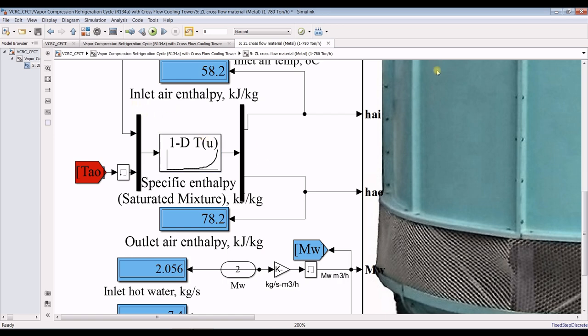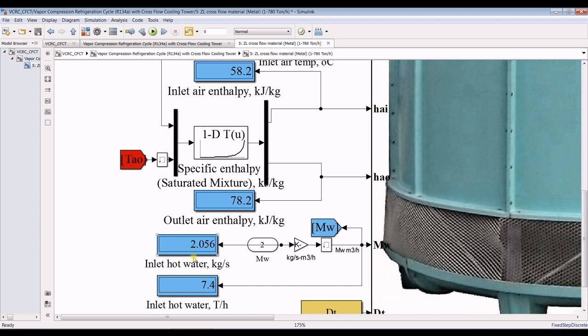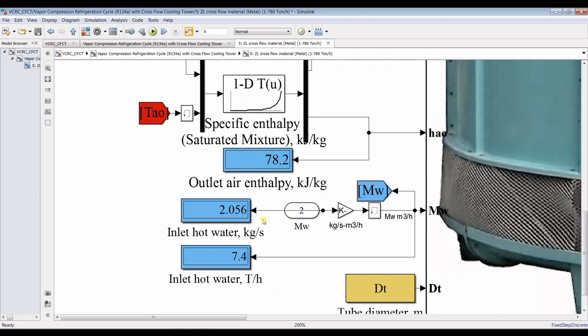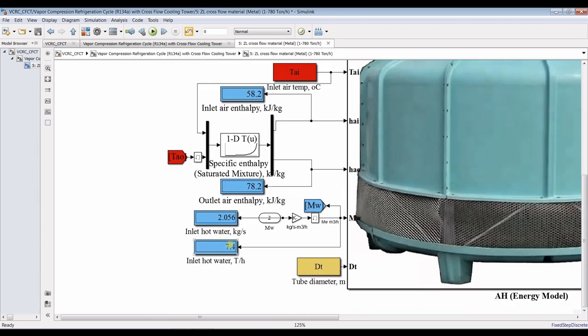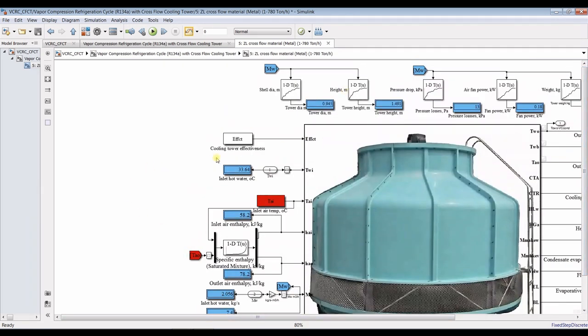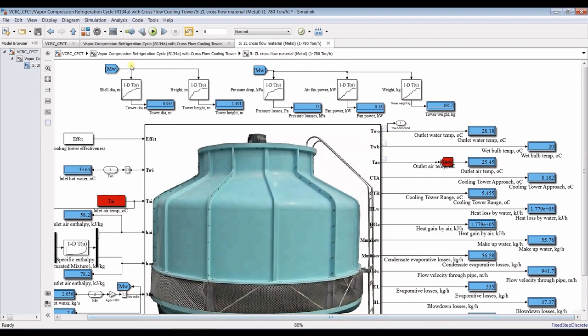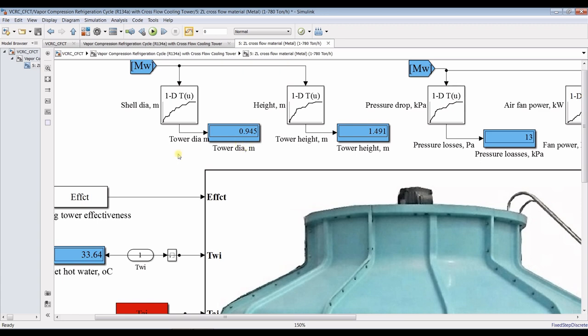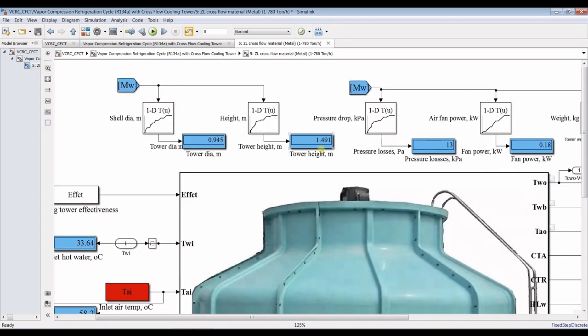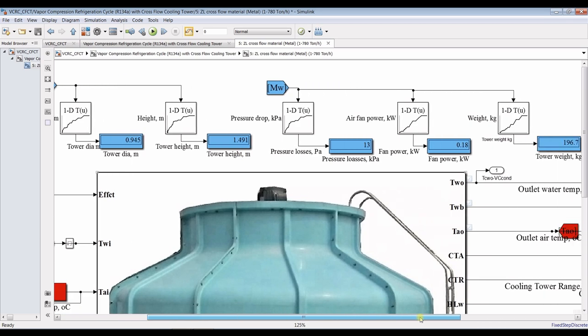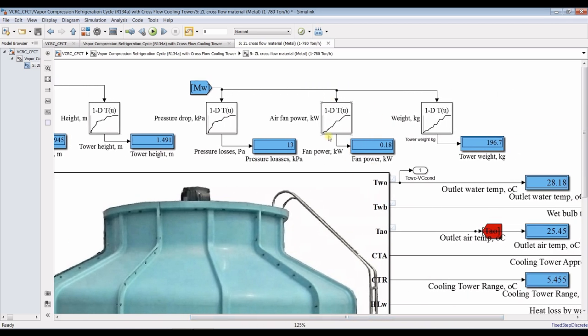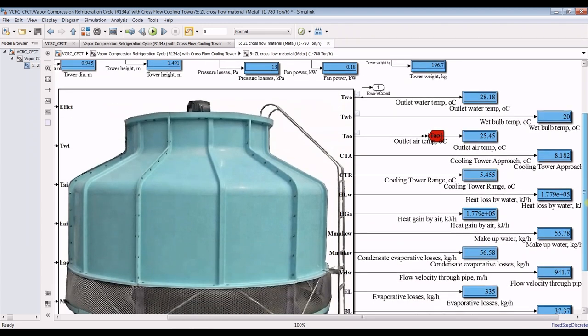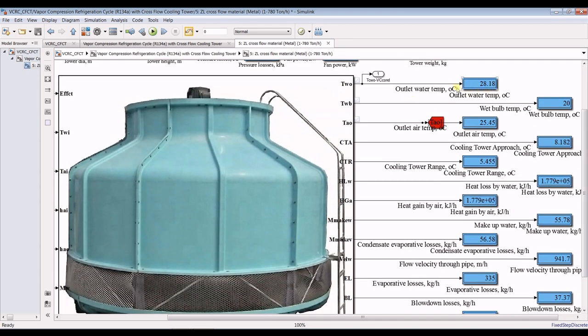Okay, and this is your hot water coming from the condenser, as we showed before. It's 2.05 kilogram per second. It's around 7.4 ton per hour. Okay, under these circumstances or inputs, these are our outputs. This is tower diameter and height of the cooling tower. And this is the fan power of the cooling tower. This is fan power and total weight of the cooling tower. Okay, small cooling tower. And this is your output water temperature.